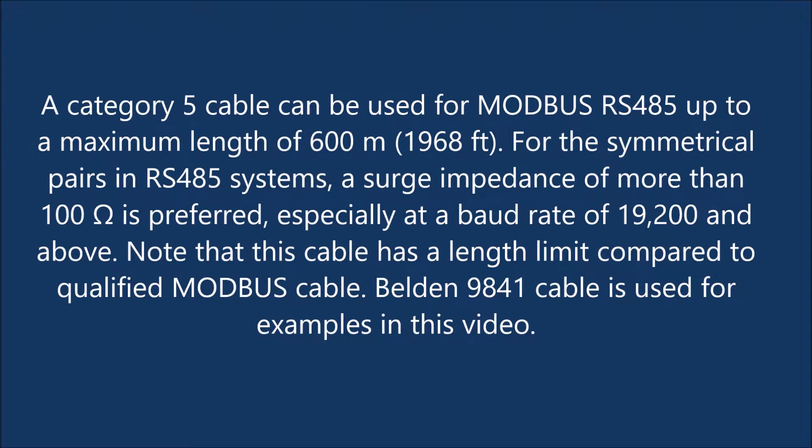A Category 5 cable can be used for Modbus RS-485 up to a maximum length of 600 meters (1,968 feet). For the symmetrical pairs in RS-485 systems, a surge impedance of more than 100 ohms is preferred, especially at a baud rate of 19,200 and above. Note that this cable has a length limit compared to qualified Modbus cable.